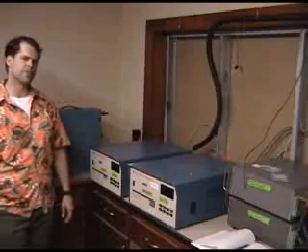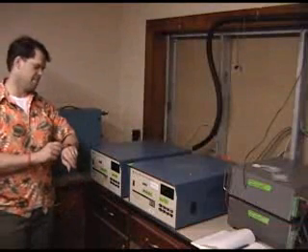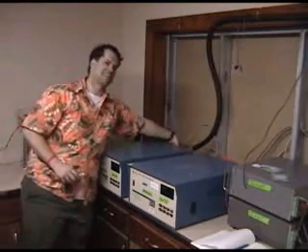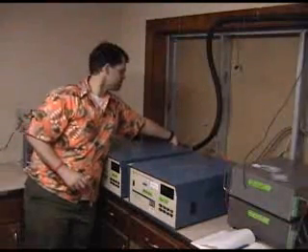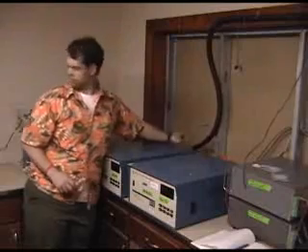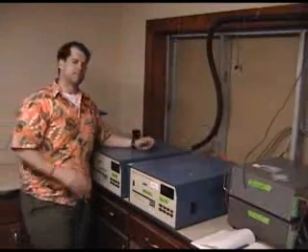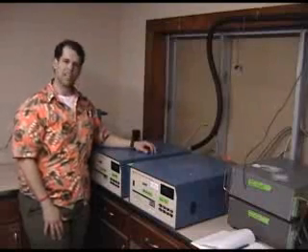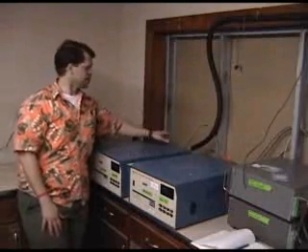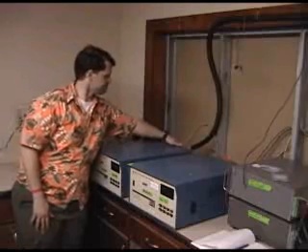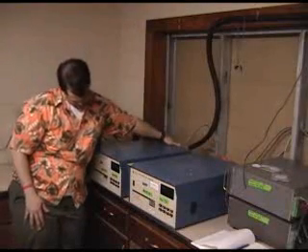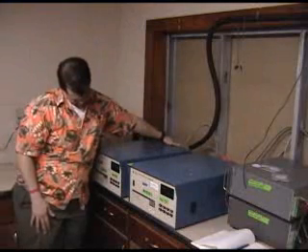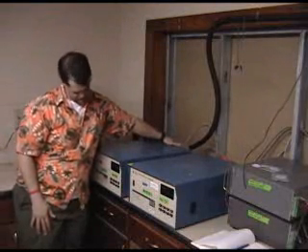Now we want to see the pressure drop below 250 in about a minute. And how we're going to do that is we are going to disconnect this ambient sample line. And some people have special little nuts that have blocked stuff or plugs. You can just use your finger in this case. Taking note of the time and see if it drops below 250 in about a minute.